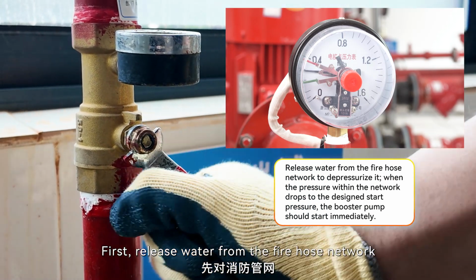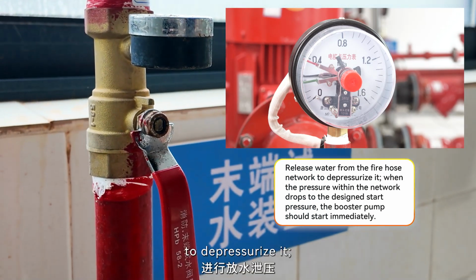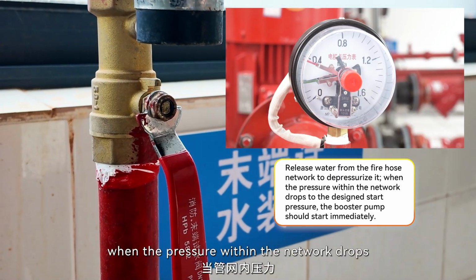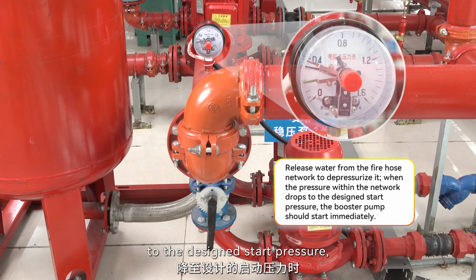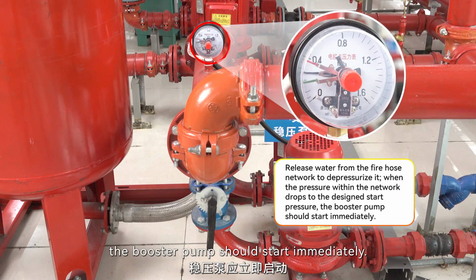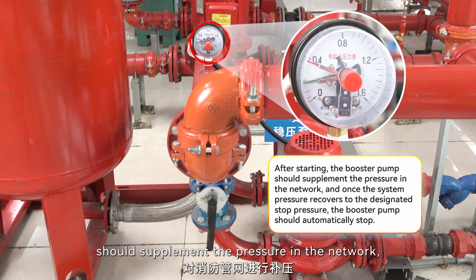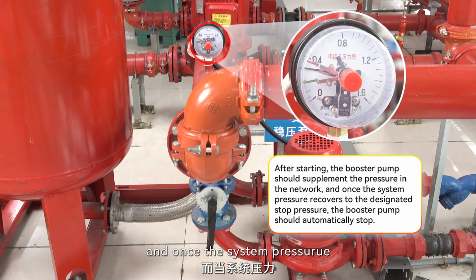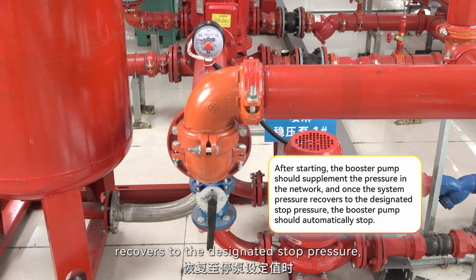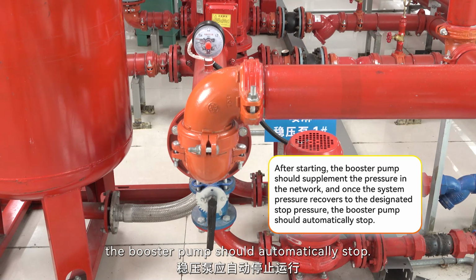First, release water from the fire hose network to depressurize it. When the pressure within the network drops to the designed start pressure, the booster pump should start immediately. After starting, the booster pump should supplement the pressure in the network. And once the system pressure recovers to the designated stop pressure, the booster pump should automatically stop.